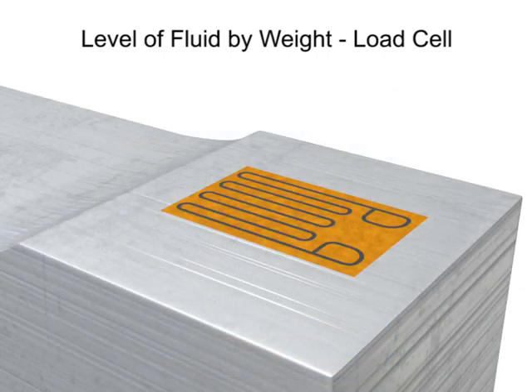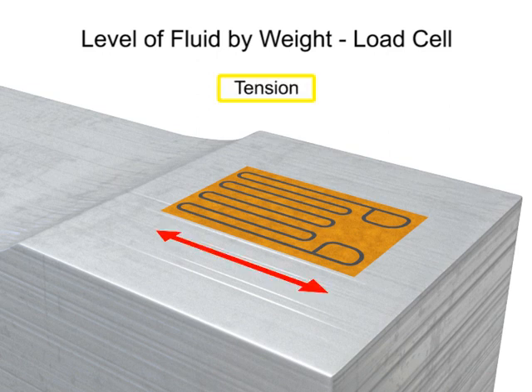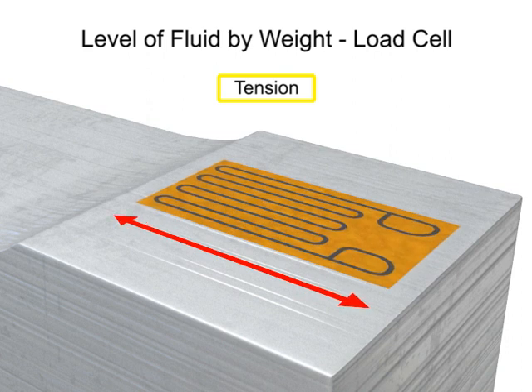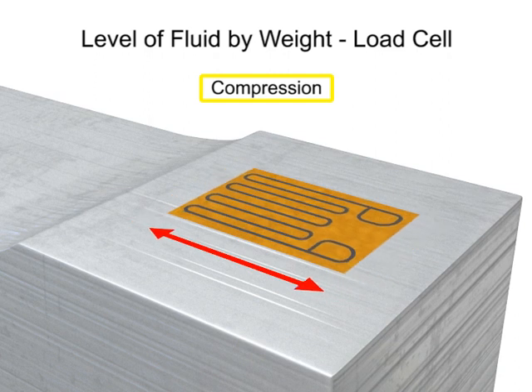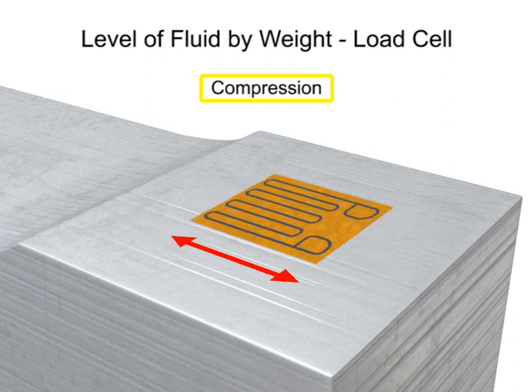As force or weight is applied to the load cell, the strain gauge deforms and causes the electrical resistance to change. In tension, the area narrows and the resistance increases, and conversely, in compression, the area thickens and resistance decreases.